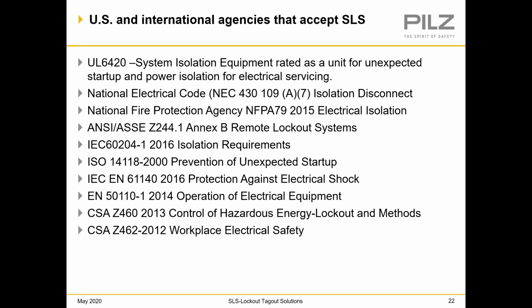And then there are international standards, the IEC standard, the ISO standard, and then a couple of European Union standards, the EN standards, which are IEC standards and European Union standards, and a couple of Canadian standards, the CSA standards on the bottom. So there's a lot of acceptance around the world using this system as a solution for all of the negative things that traditional LOTO provides. This provides the solutions using all of these standards.